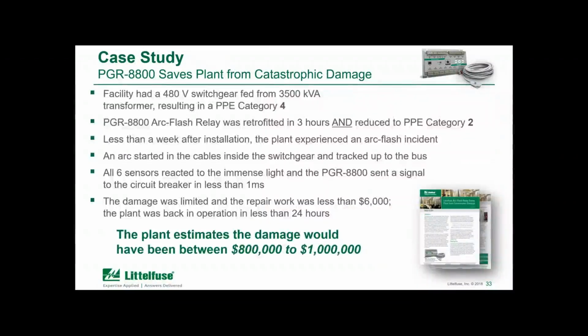So just as a case study that I wanted to share, this showed the significance and the savings that can be achieved by designing in a product like an arc flash relay. We worked with an end customer that had a facility where their arc flash analysis determined that their 480 volt switchgear, which was fed from a 3.5 MVA transformer, had a PPE category of 4. And this meant that the worker wasn't allowed to approach the cabinet with the door open.